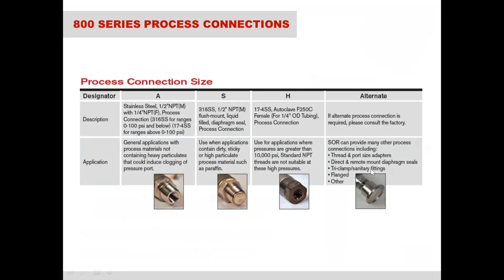Now looking at some of the process connections that we offer. So for the 800 series or the 805 and 815 series, we offer a standard A process connection. This process connection gives you a half-inch NPT male as well as a quarter-inch NPT female on the inside, so it's a dual process connection. We also offer the S port, which gives you a flush face diaphragm seal on there, so that if you have an application that has dirty or sticky or high particulate matter in there, this is a way to prevent that pressure port from clogging and getting buildup in there and ultimately altering your signal.